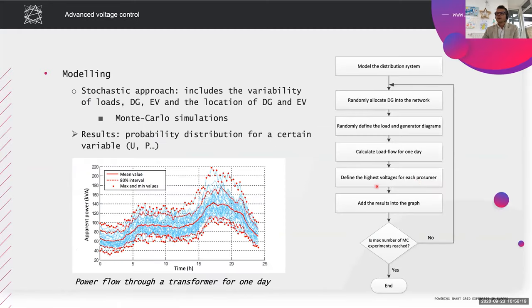What you get as a result, I'm showing only one result. Of course, if you use probability curves as the input, you get probability curves as an output. And this is the probability of a loading of a medium to low voltage transformer. If you again take a look at an evening hour, around 6 or 7 in the evening, you can see that the power through this transformer will be somewhere between 90 kilowatts and 200 kilowatts. And clearly the most probable results are in between. And these are results you can also use for network planning.